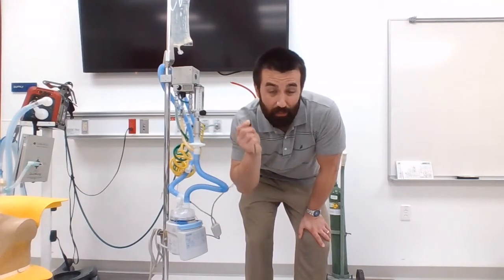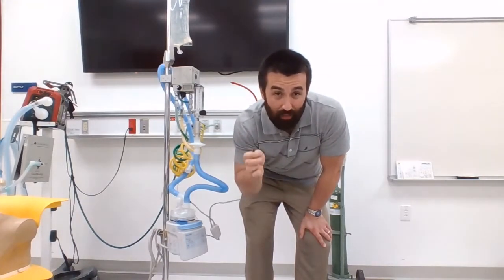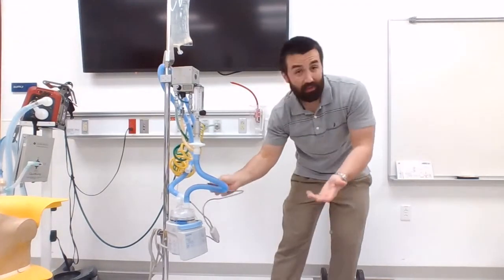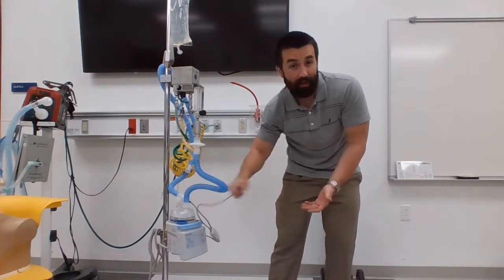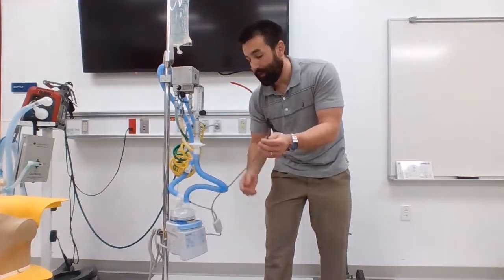It prevents that expiratory gas from having condensation problems. The beauty is you cannot hook these things up wrong. If you look, there'd be 3 holes on the back of this. There'd be only 2 on the expiratory side, and we'll get into that as we get into ventilators. So we can leave that one hang. Once again, that's energizing the circuit.